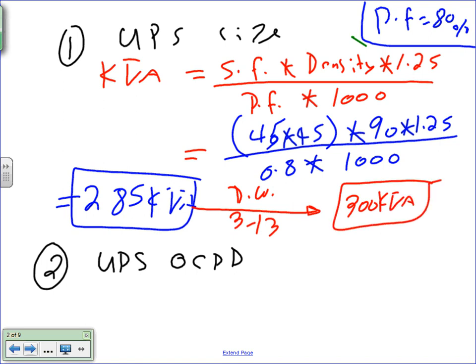Again, these are for practical reasons to do the calculation. If you go to a different manufacturer, they might have different sizes in between. So, for example, instead of 285, they might have 290. So you use a 290. But just to standardize, so we can do some calculation. This is close to the truth, but might not be all the truth here. So my size is 300 kVA. So I'm going to go buy a UPS, 300 kVA UPS.